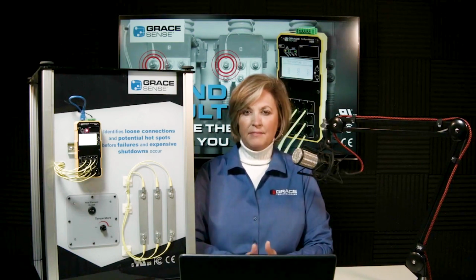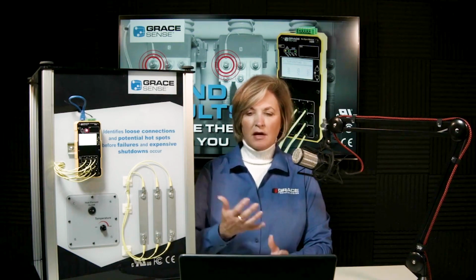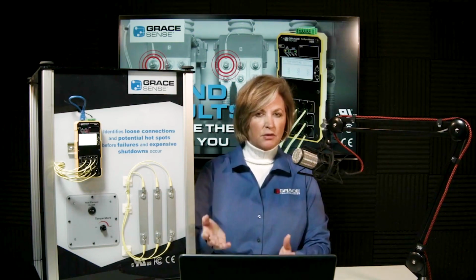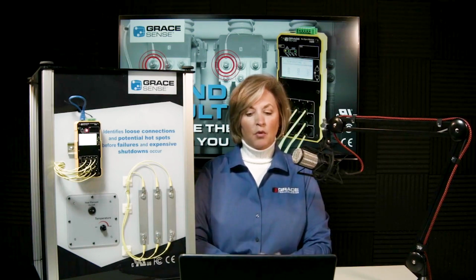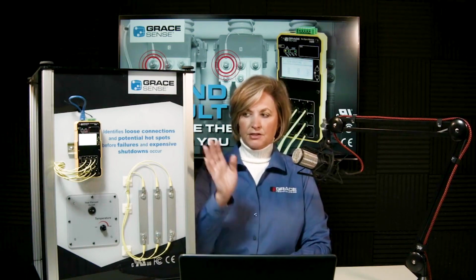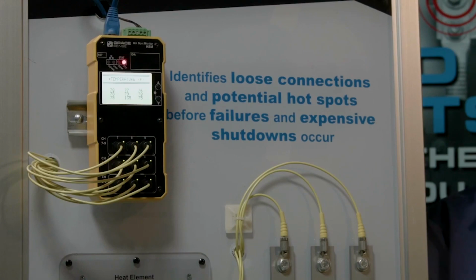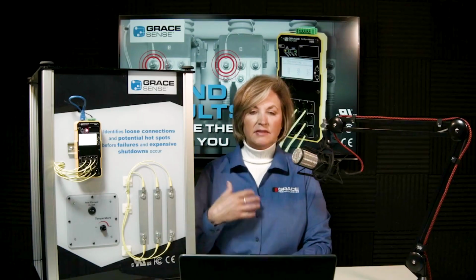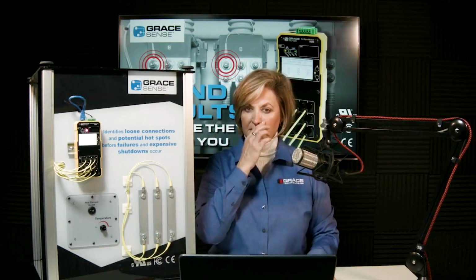So we typically have fiber on hand all the time. So calling us up and saying we need it because we have a shutdown, and it's only going to be down for a few days, would be a great opportunity to also get this product in there. Then we can come back and install the electronics and do the setup and all that at a later date. But it's not as critical to get the electronics in as it is to get the probes attached inside the high voltage areas.